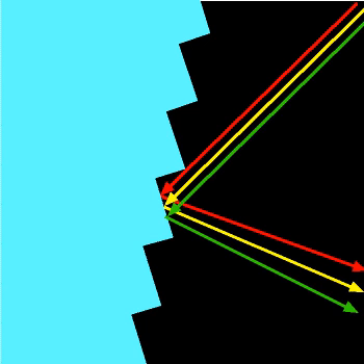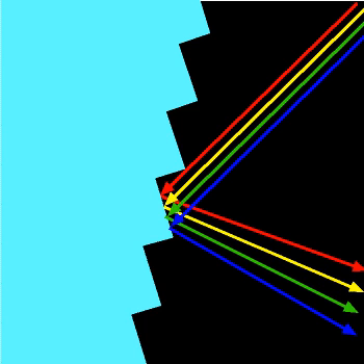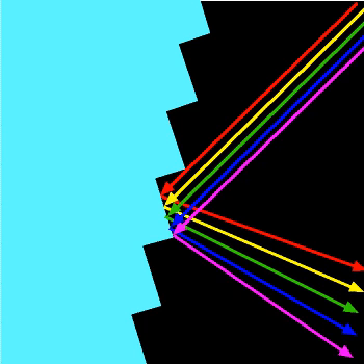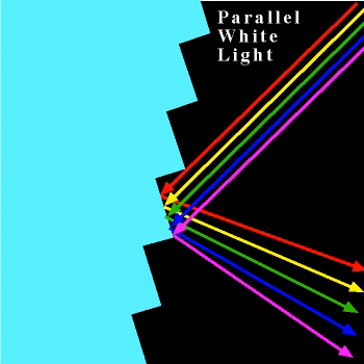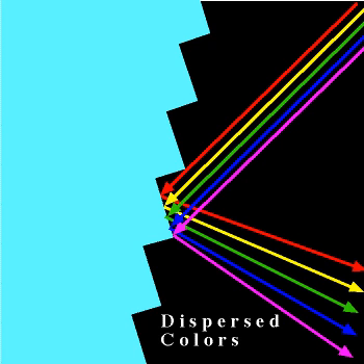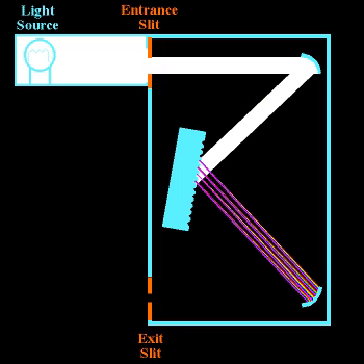An extremely important thing happens at the grating. The reflection process involves constructive and destructive interference of the incoming light rays bouncing off the reflective surface. This separates the individual wavelengths from the white light source into rays no longer traveling parallel with each other. Each wavelength is reflected at a slightly different angle off the grating surface and aimed toward the second mirror. This light separation process is called dispersion and is the heart of the monochromator. Individual wavelengths are separated in space.